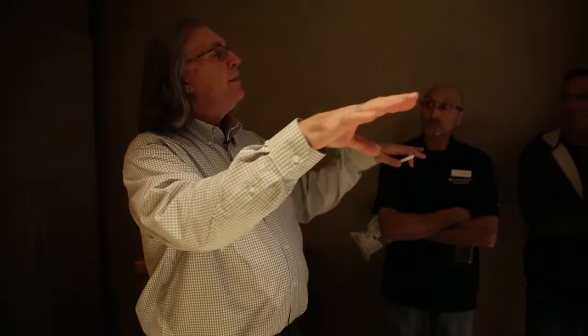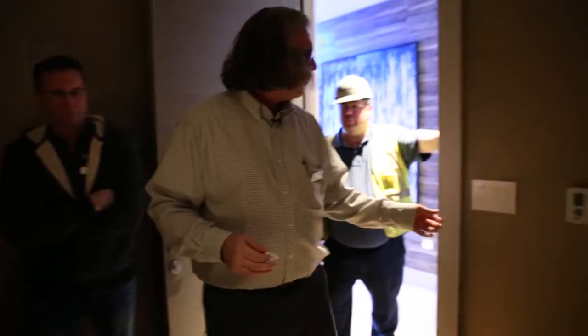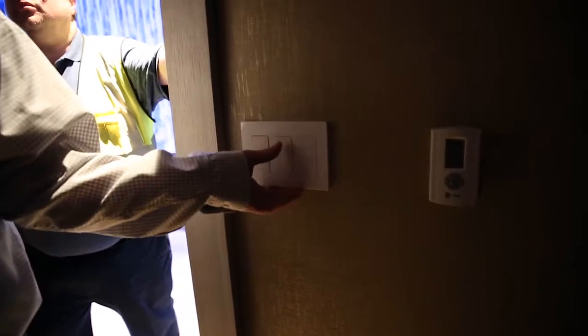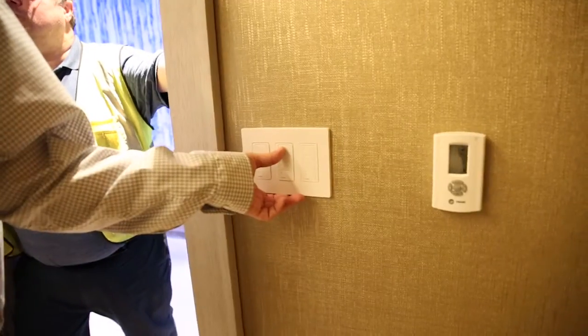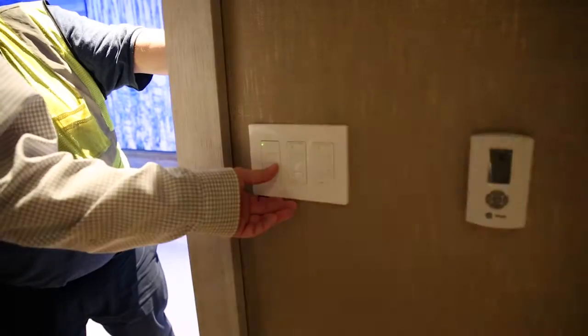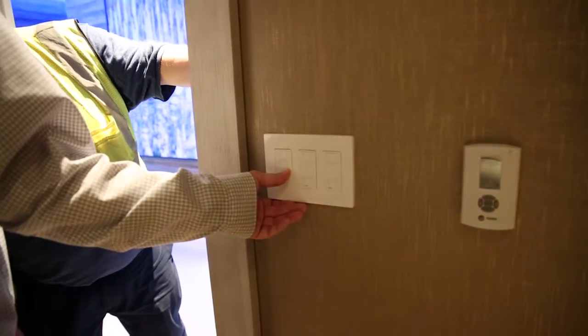Now this room, why don't you guys come in, because this room is definitely different than the other ones. We call this room zone control. The other rooms were scene control. You pushed a button and you controlled all the lights, so you sat there and said, I have a presentation scene, I have an AV scene, and all the lights change. Here, each one of these only controls one zone. If you take a look at it, we still have a couple of lighting issues here, but this one is going to control these lights here, all right? This one here is going to control the side wall wash, all right? Each one of these has a raise lower button on it. So if I come here, I lower it, I can lower it, all right?